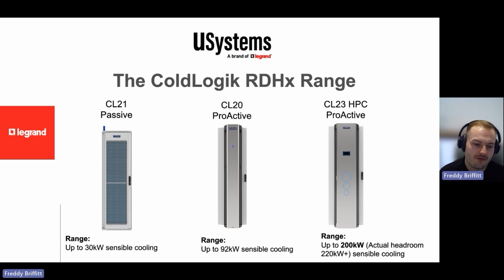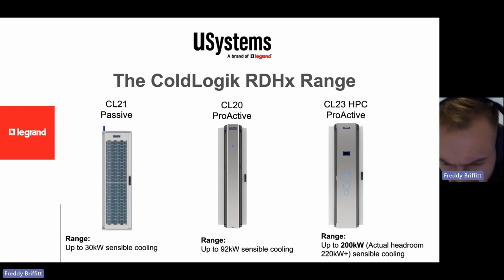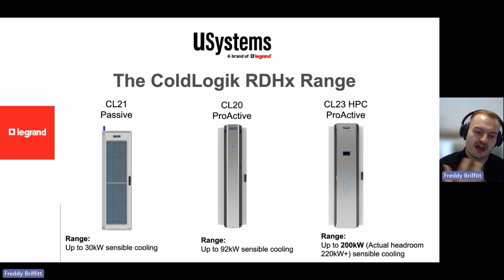And then finally, we have the passive. So the passive door itself, as you can see, is simply a coil. It doesn't have fans. The passive door itself relies on the servers within the rack being able to produce enough static pressure to push the air over the coil. Now, that's okay if you can guarantee the airflow from the back of your servers. We have some customers that have got some older servers that they're deploying on a rollout that has exactly the same airflow every single rack. And ultimately, if we only have to run one set of fans, it's going to be more efficient than running two sets of fans. So that works really well for them. But for most of our customers, we recommend an active door because the newer servers, the newer fan sets that have come out, don't necessarily produce enough static pressure to push that air over the coil.